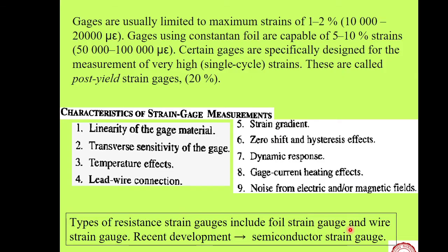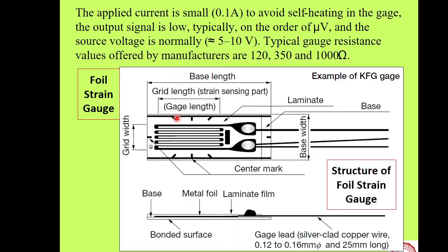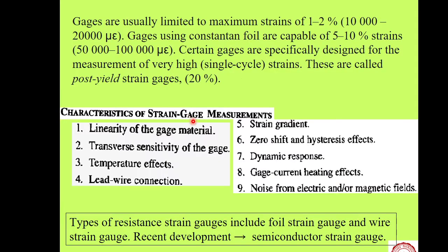That is not possible because there is a heating effect of that current. And for excessive heating, the wire of the strain gauge is very thin, it can burn out. That sort of possibility is there. Of course, the local heating of the strain gauge in this region will be generated. That again will affect the gauge factor. So, these are the factors or characteristics, and noise from other sources.